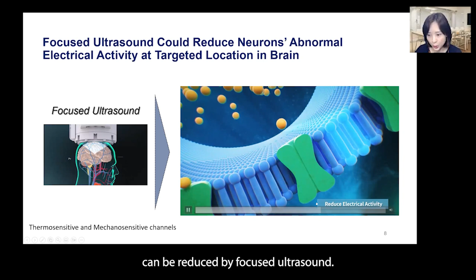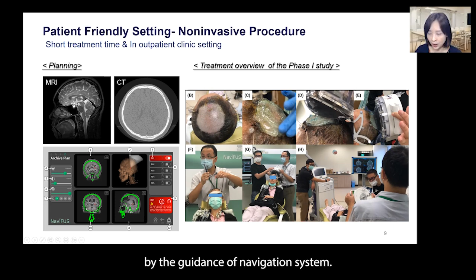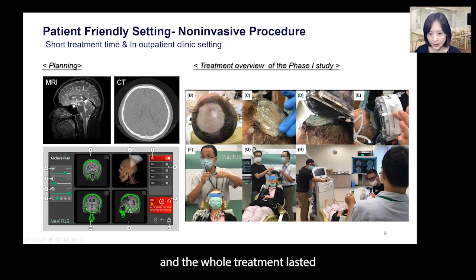Here, I want to introduce how we did the treatments in our phase 1 clinical trial. We need an MRI and a CAT scan before the treatments. We make a plan and simulate the situation. We are going to do the treatments. We have to calculate the bone density and the energy penetrating to the targets. On the day of treatment, the patient has to shave the hair, and the neurosurgeon will hold the transducer and adjust the position and angles by the guidance of a navigation system. All this procedure can be done in an outpatient clinical setting, and the whole treatment lasts 1 hour, including setting up the machine.